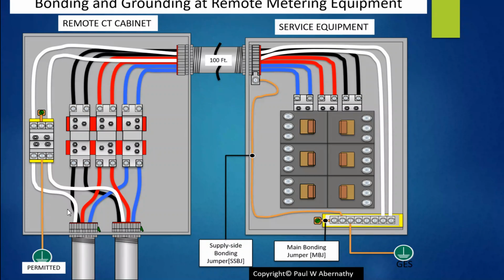Again, it's permitted to do it over here. Here's the one where we generally like to see in the application. Over here is permitted. The reason we say this one's permitted is because we would prefer it to be done here at the service equipment over here than over here, because this is not service equipment. None of this is service equipment, okay? All right. And it just increases a hazard by doing it over here and not doing it over here. We really prefer to have it here in this application.